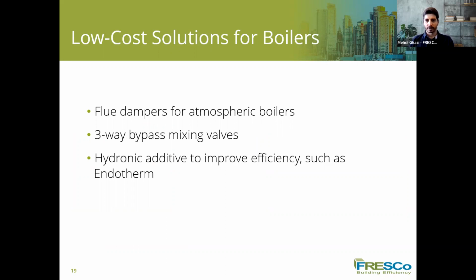Some low-cost solutions for the boilers could be an automatic flue damper, which closes when the boiler is not firing and holds the heat in, much like a lid on a pot. Because in older buildings, the standard in equipment without a flue damper is that air is drawn through the boiler and out the flue by convection, so that leads to wasting energy. To prevent that, we want to have a damper and to prevent the boiler from turning into a radiator. We don't want to waste that amount of heat.